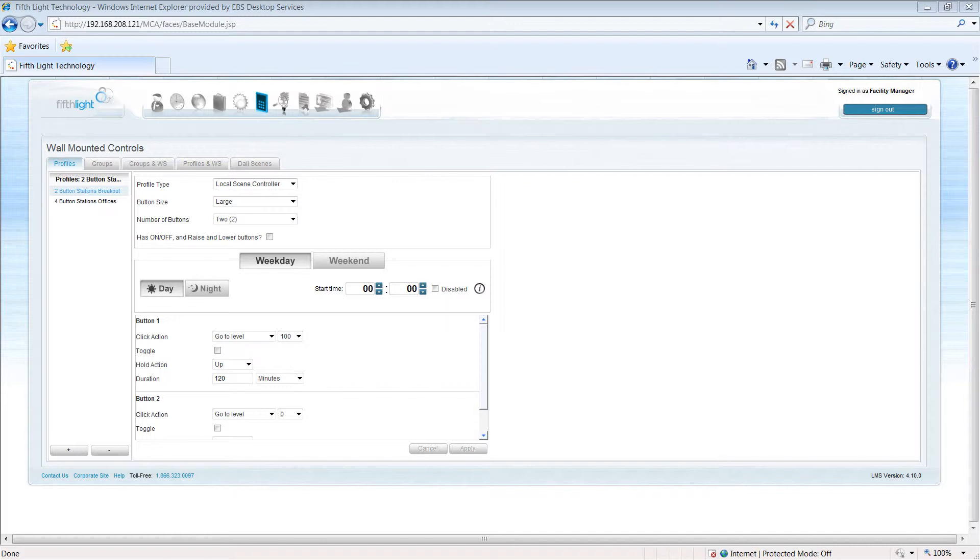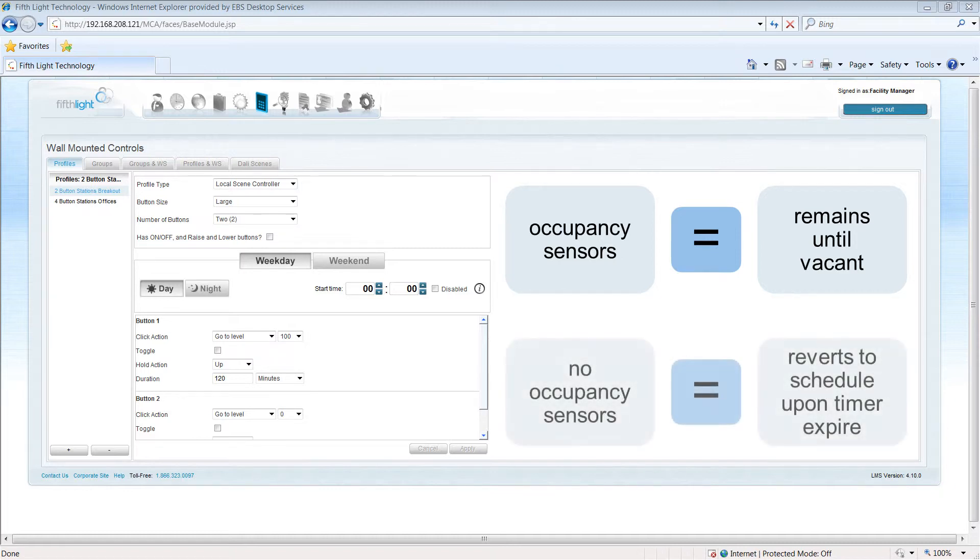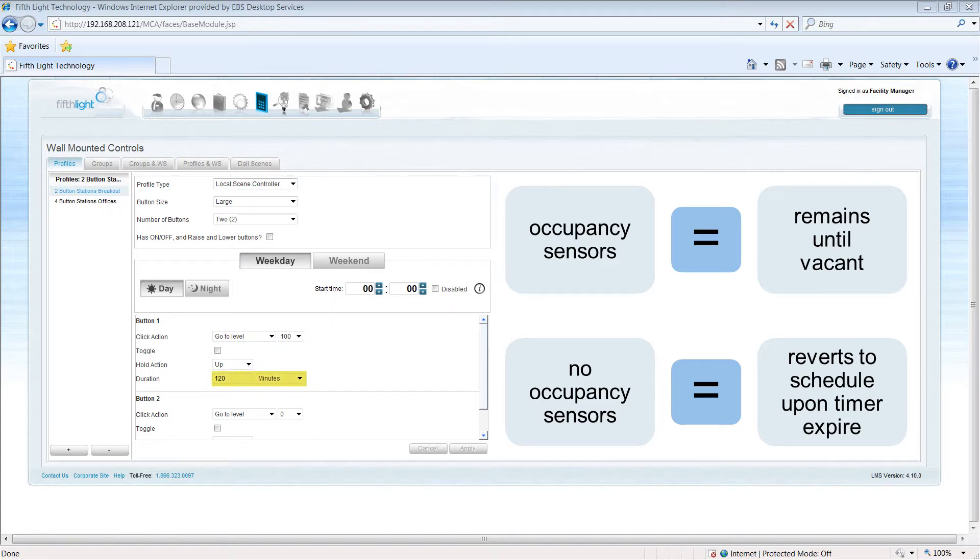Once a wall station button is pressed in an area containing occupancy sensors, lighting typically remains at the requested level until the area is vacant. For locations without occupancy sensors, the light level typically reverts to the scheduled level once the timer expires.